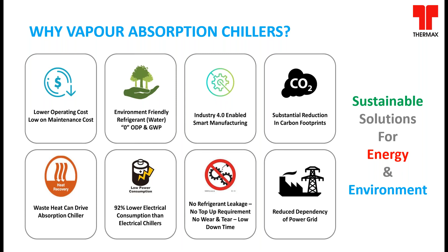Now we will try to understand how this chiller works. For this, we have to start with the evaporator, wherein we have a refrigerant, which is the DM water, which will be used to remove heat from the process water. From your air conditioning systems, chilled water would be circulated through the evaporator tubes, and the refrigerant would be sprayed on it, which will then pick up the heat from the chilled water and cool it to the required temperatures. Now the heat gained by the refrigerant will be used to convert it from liquid phase to vapor phase. The refrigerant will boil out and we will have refrigerant vapor getting accumulated inside the evaporator.